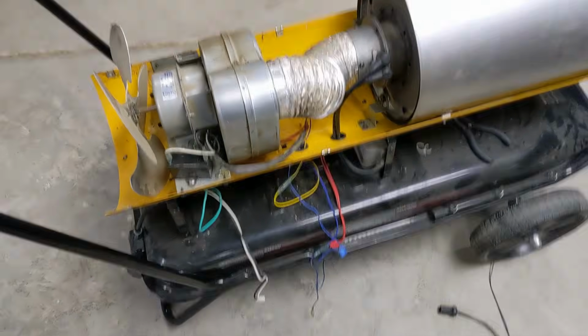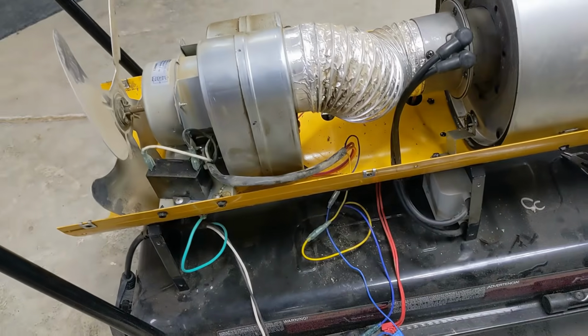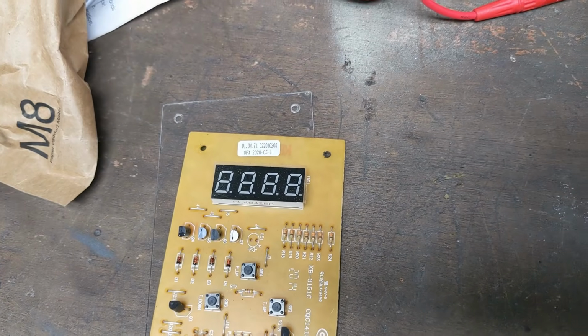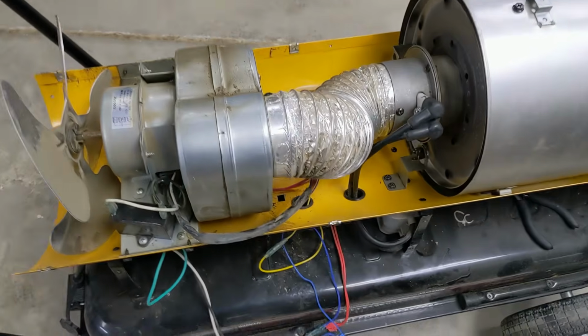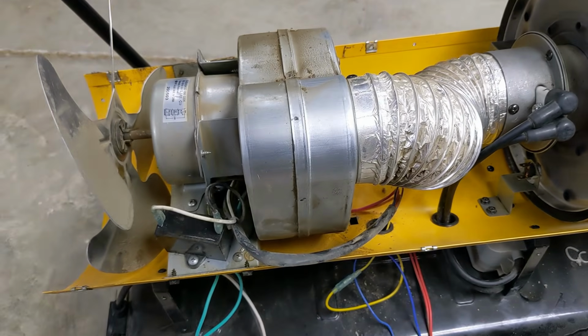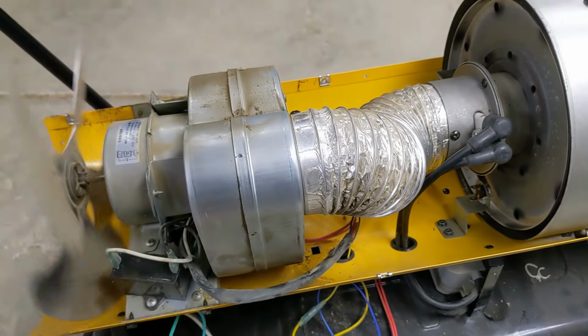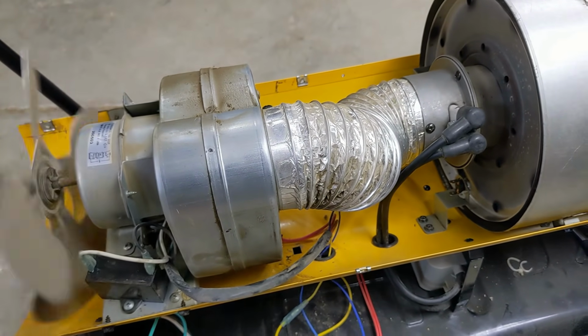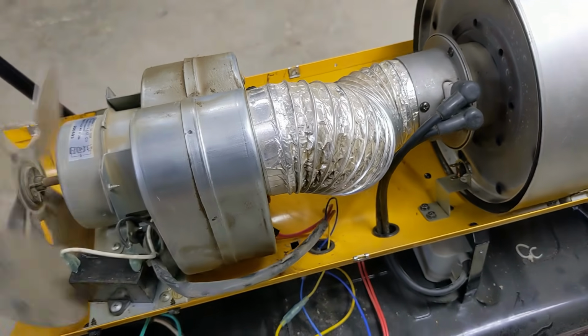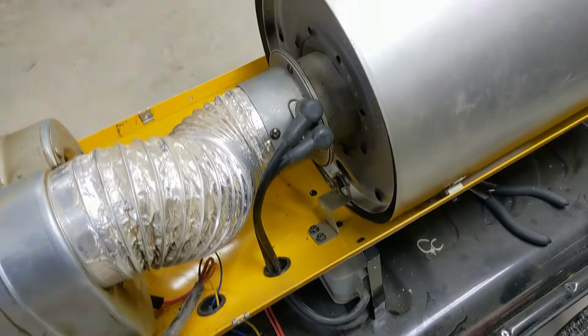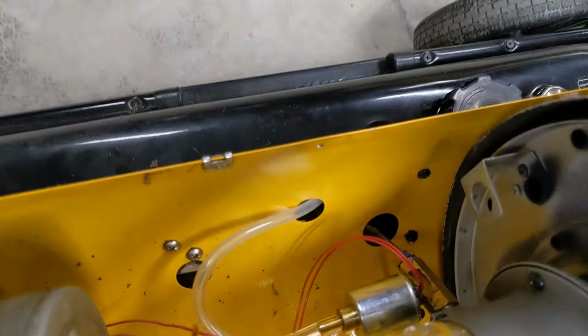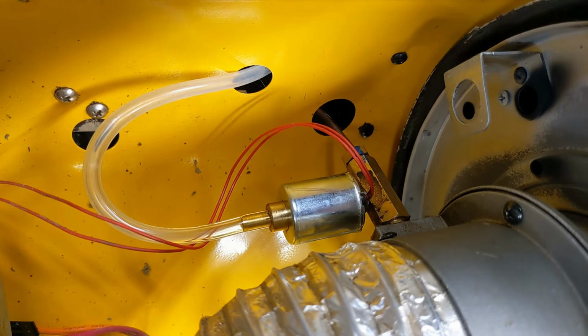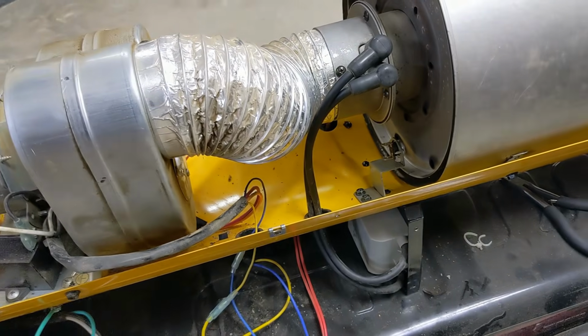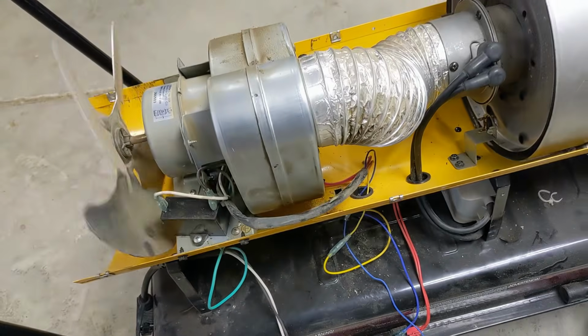Here's the way a dumb thing works. Turn the power on. You set the temperature over on that board. It goes through 5 safety checks, and then it goes through a startup. And I'm not positive which one goes exactly first, but I'm pretty sure I know which one goes last. So the fan kicks on, which I think is first, and then I believe the igniter kicks on second, sparks in here, and then the fuel solenoid opens up and the pump runs, and that lets fuel in, and there you go. So what happened?